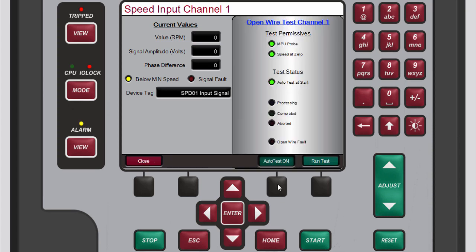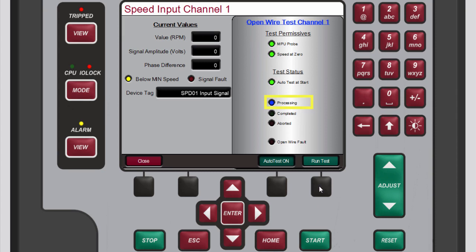Press the black function key below Open Wire Test. In the open wire test channel window that pops up, verify that both test permissives LEDs are illuminated green, and then press the black function key below Run Test. The processing LED illuminates blue shortly before the completed LED illuminates green. If the test fails, the open wire fault LED will illuminate red, as is shown here. When this occurs, you should check the wiring from the end device to troubleshoot the fault. If the controller had to abort the test, the aborted LED would have illuminated red.